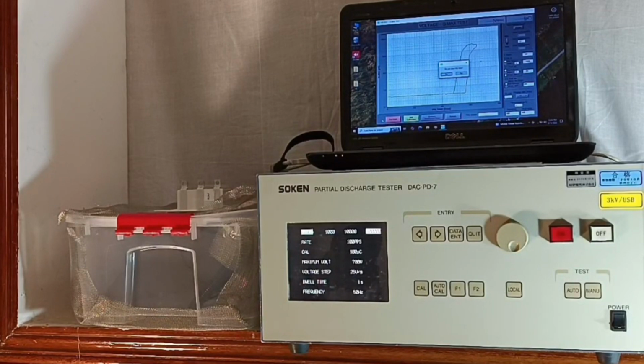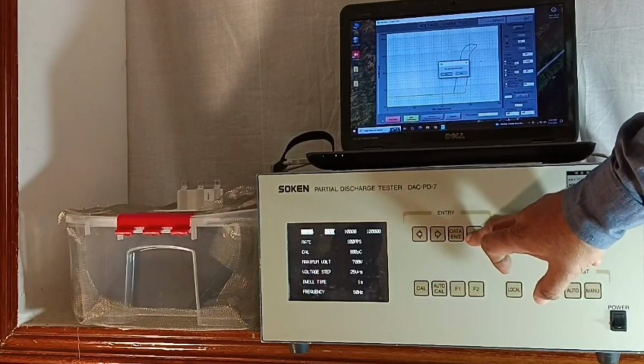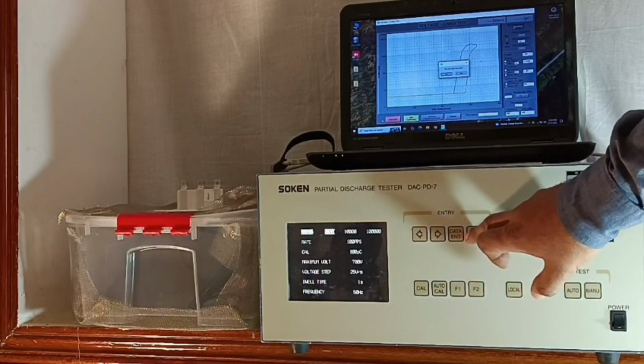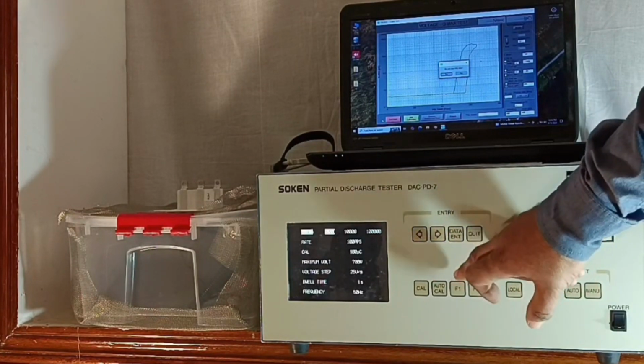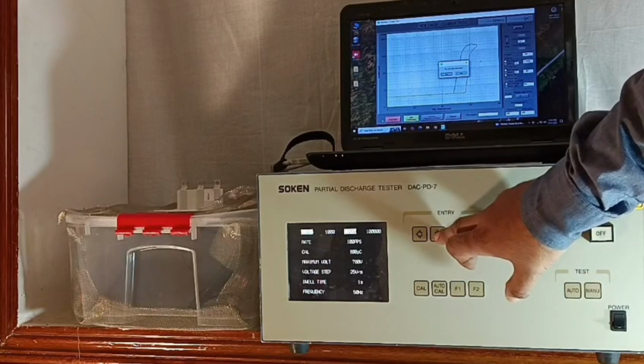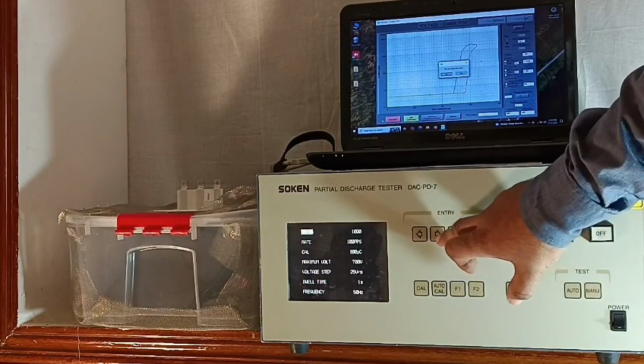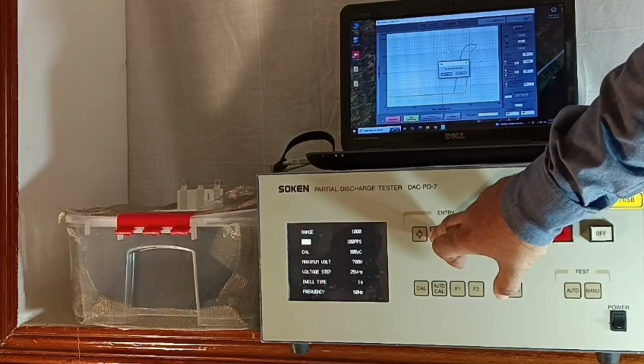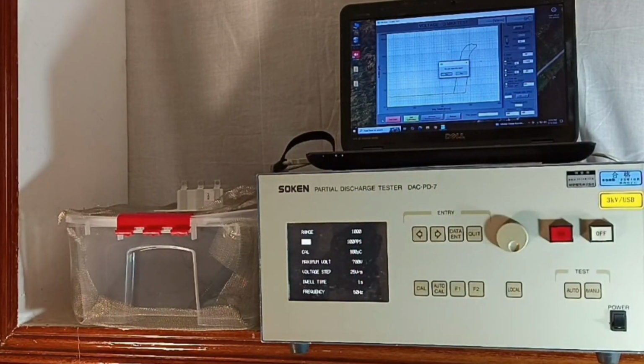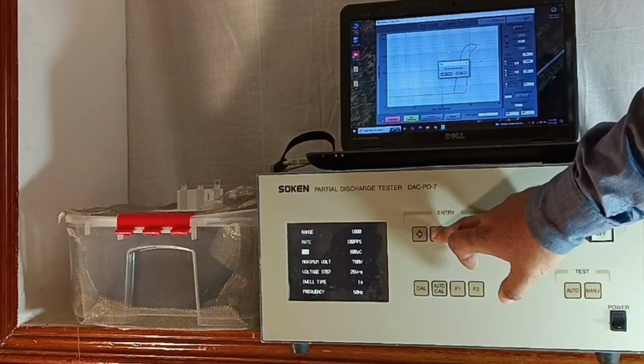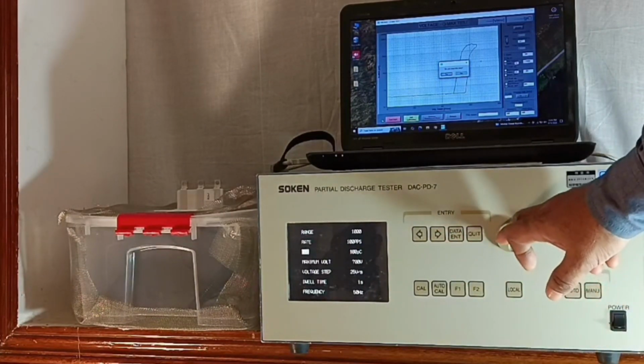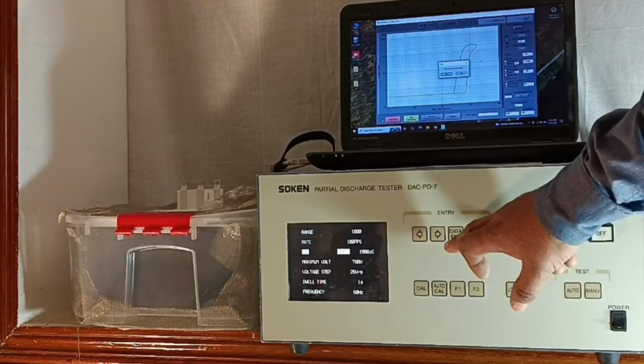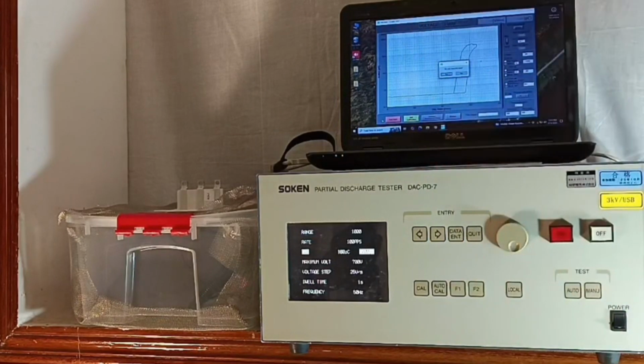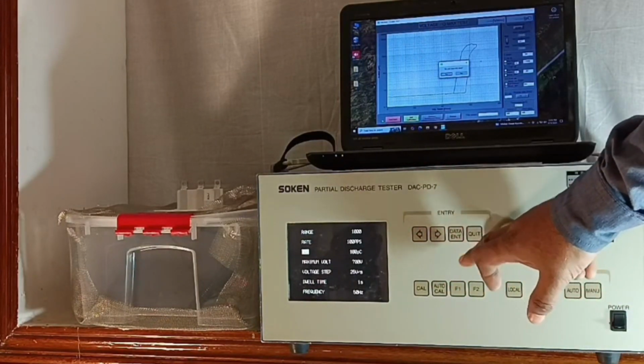Range depending on the test expected value of discharges. You can select. So now it was sent. Now I will say data enter. Then this is DC. Next is rate, that is pulse per second. Then the calibration pulse is 100 PC is selected. You can see 1000 PC also can be selected for the higher ranges. Now it was 100 PC.